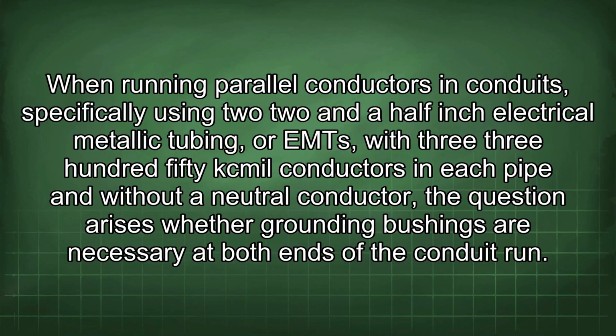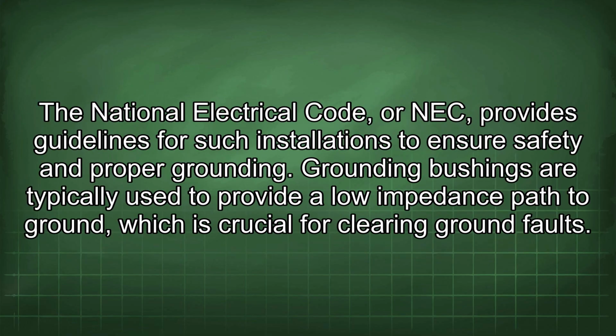When running parallel conductors in conduits, specifically using two 2.5-inch electrical metallic tubing, or EMTs, with three 350 kcmil conductors in each pipe and without a neutral conductor, the question arises whether grounding bushings are necessary at both ends of the conduit run. The National Electrical Code, or NEC, provides guidelines for such installations to ensure safety and proper grounding. Grounding bushings are typically used to provide a low impedance path to ground, which is crucial for clearing ground faults.